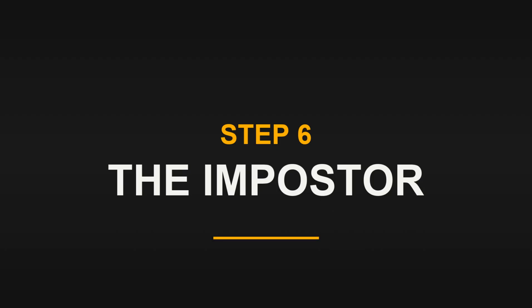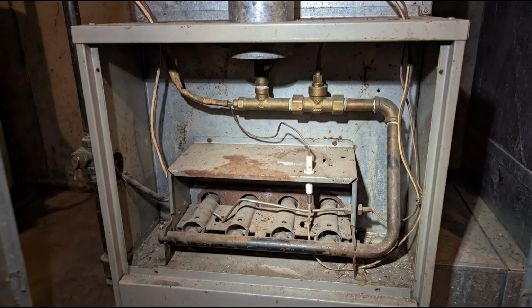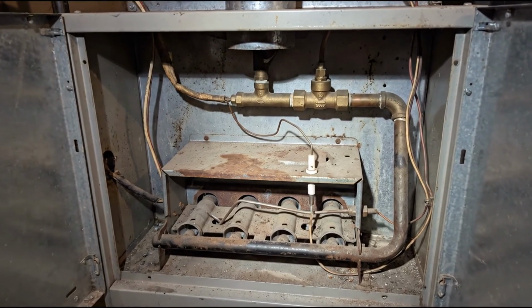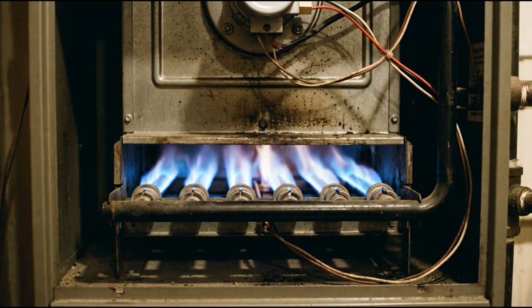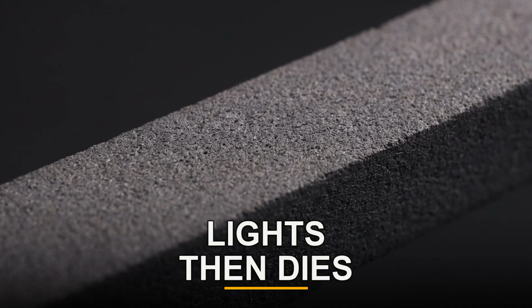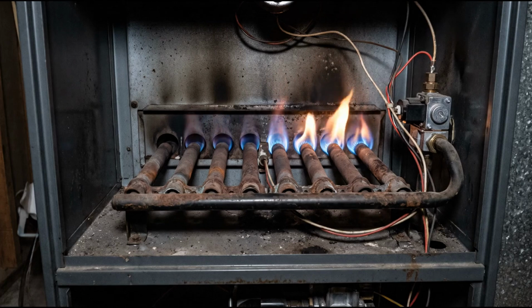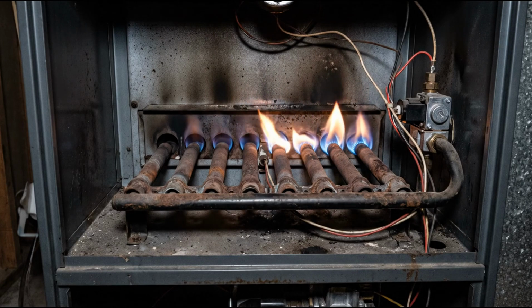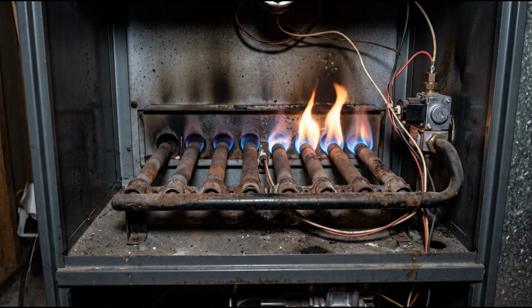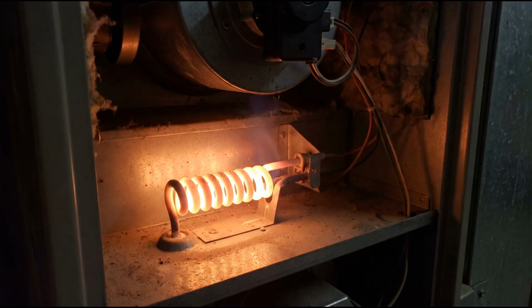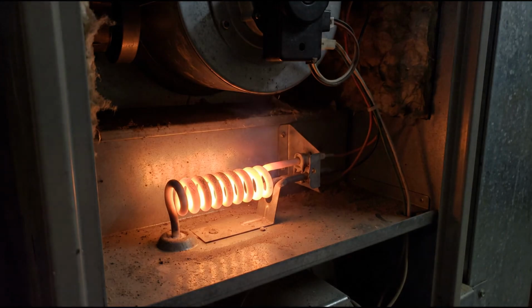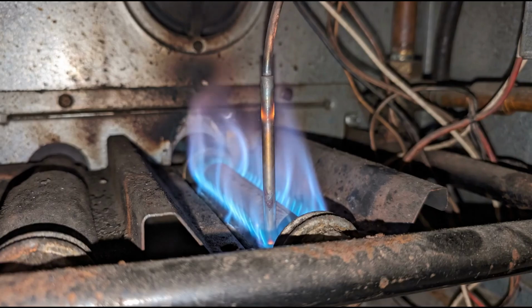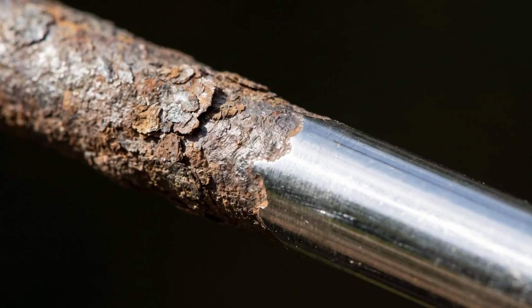Step 6. The impostor. There is one other part in that cabinet that produces almost the same story. The furnace lights, runs for 5 or 10 seconds, and then shuts back down. Lights, then dies, over and over. If that is your pattern, the burners do light and then quit. Your igniter is fine. That is the flame sensor. It is an even simpler part, a thin metal rod that sits in the flame and tells the control board the fire is actually burning.